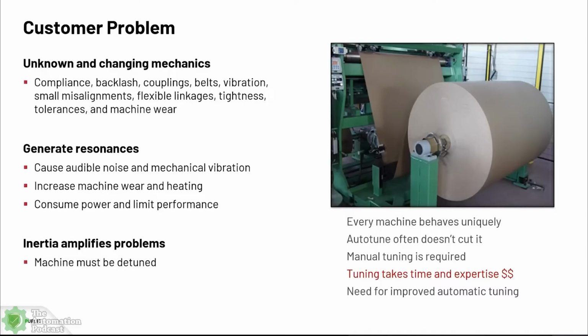Oftentimes you're using auto-tune. Auto-tune is a great technology for the drive to understand the motor. Unfortunately, it's not a great technology for the drive to understand the application. So additional manual tuning is needed to make those small but important changes to get the best performance. But of course that takes time, it takes an expert. We talk about the aging workforce and those folks that have 30, 40 years of experience doing this. Well, what if I've got somebody with less experience? Now it's going to take them even more time, or I have to pay for one of those experts to come in. So the whole idea is we need an automatic tuning capability.